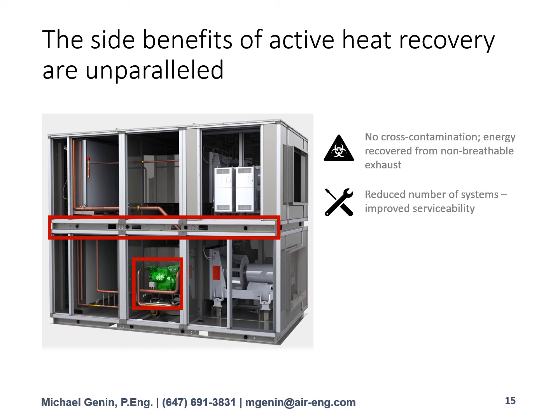The other question I get asked is, well, isn't this active heat recovery more complicated, more costly to maintain? Just because it's a new concept doesn't mean it is more complicated. In fact, it's quite the opposite in this case. If you think about a comparable DOAS unit, you're going to have a gas heat or electric heat section. You're going to need an energy recovery device like a heat wheel, and then you're going to need some kind of cooling, if you want cooling, to compare apples to apples, and that's going to occur as a DX system. That's three systems that need to be maintained. With fresh air, there's only one system, and that's a refrigeration system, which is a huge advantage.